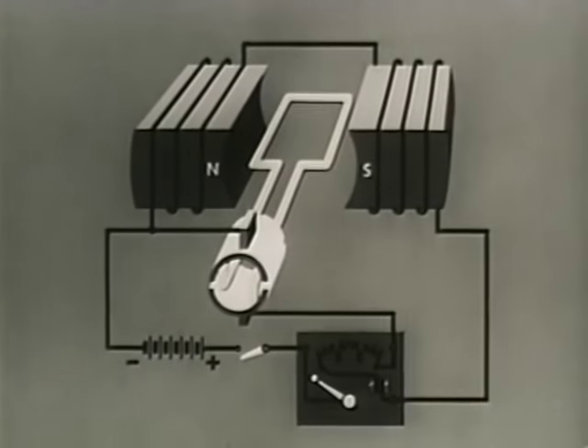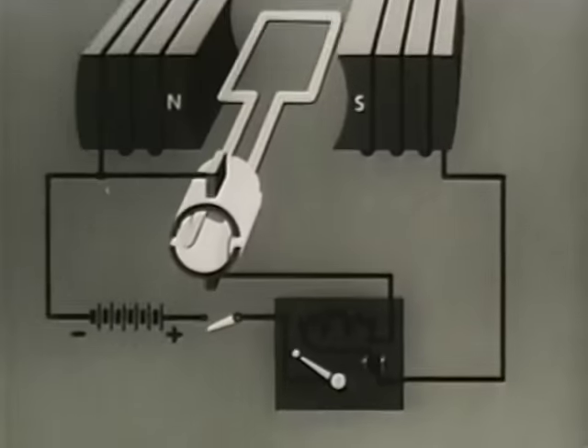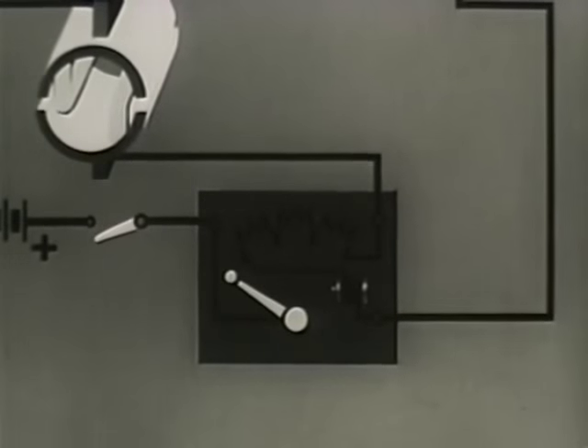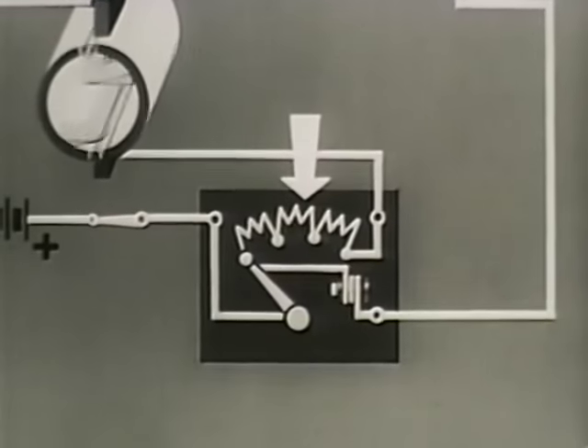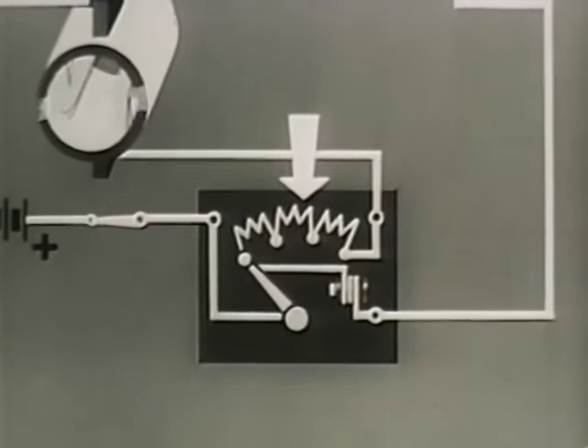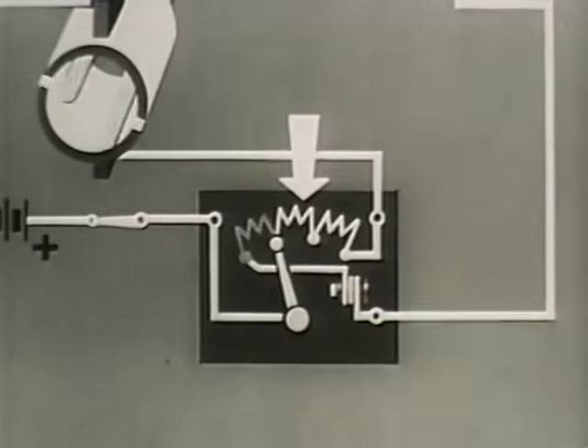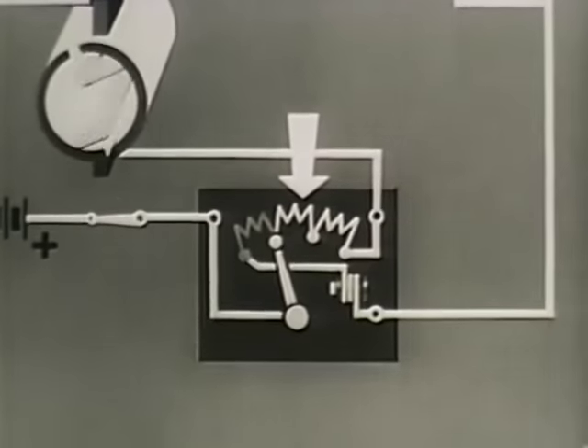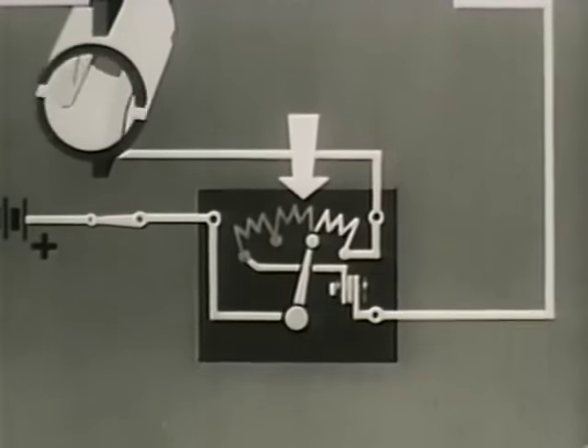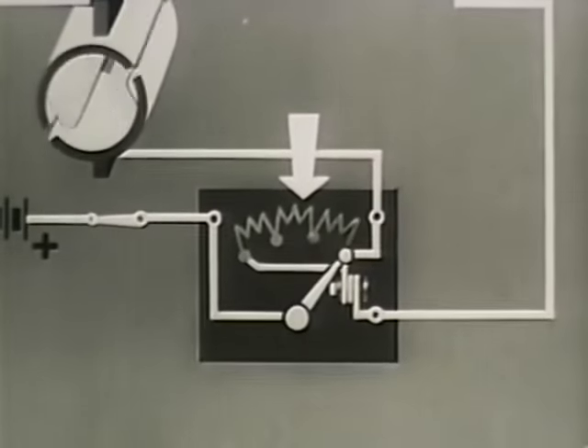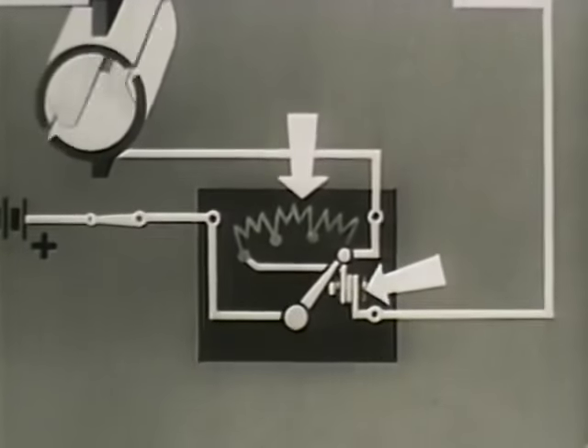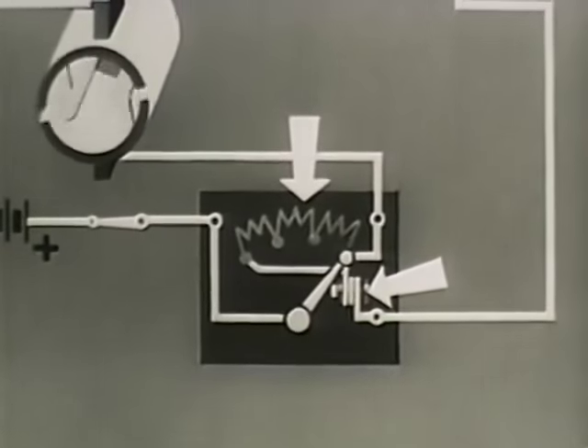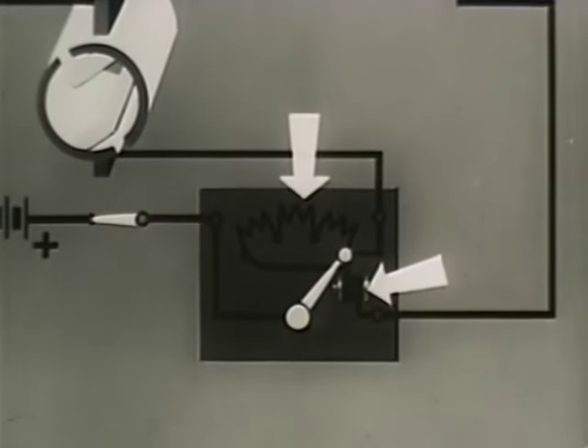Starting boxes are used with DC motors in order to avoid applying full current before the CEMF is built up. Here is a basic shunt motor with its starting box. In the starting position, the circuit to the rotor windings is closed through a series of large resistance coils. As the lever of the switch is moved, rotor speed and CEMF build up gradually and the resistance coils are subsequently cut out until running speed has been reached. The lever is held in the fully open position by an electromagnet. If for any reason the power should fail or the field coil open, the electromagnet becomes de-energized and the lever is returned to the starting position by spring action.